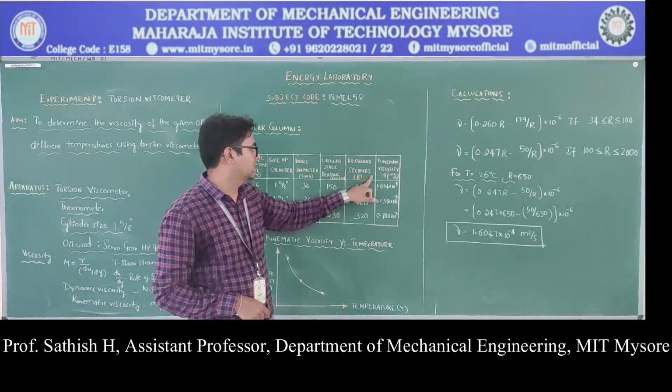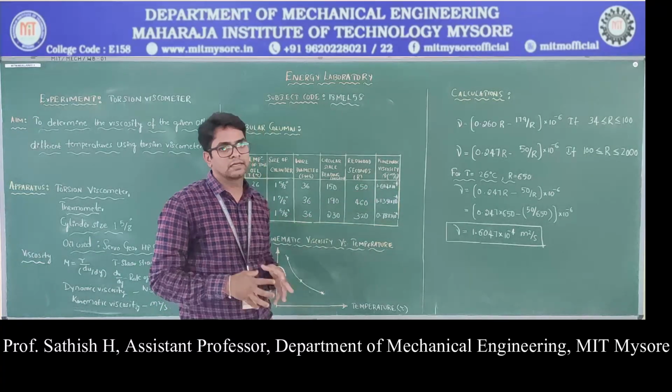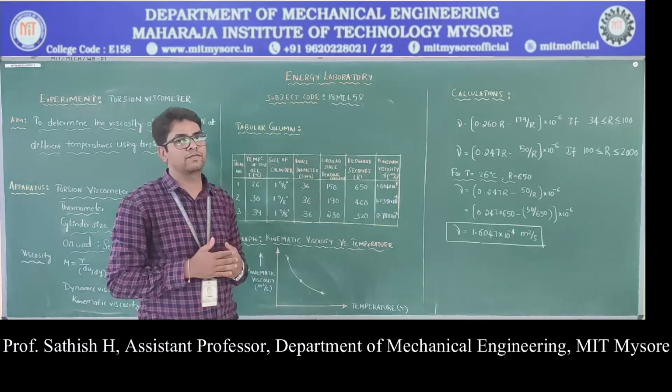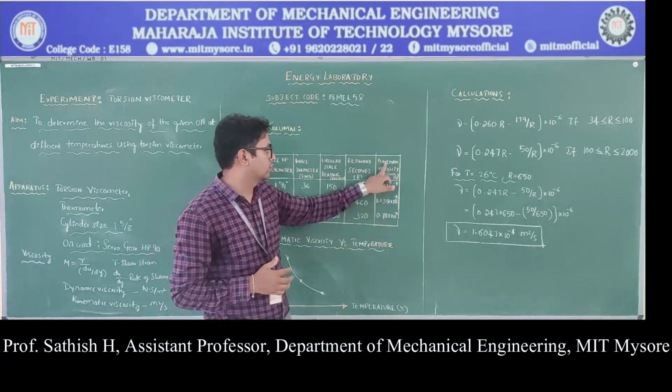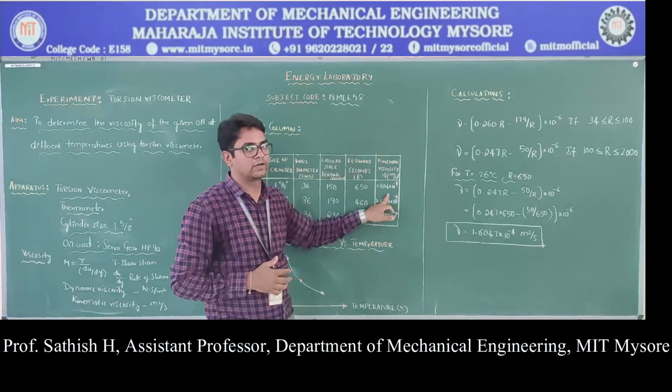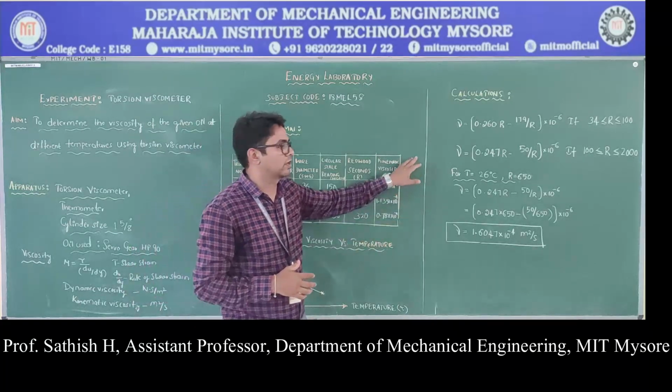And then this is Redwood seconds. That is from the chart we have noted this reading, and then we use this formula in order to calculate the kinematic viscosity here. So what is this formula? Let us look into this one.